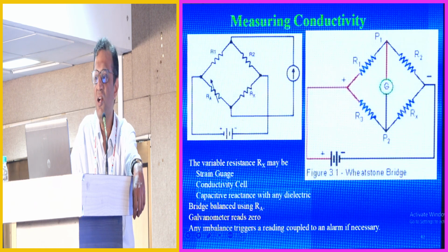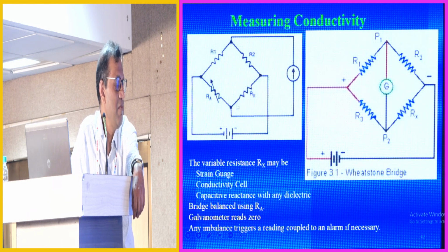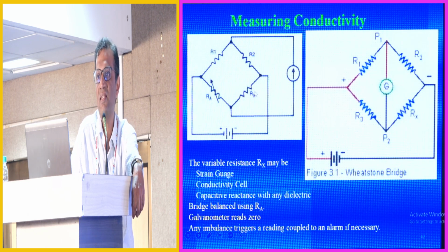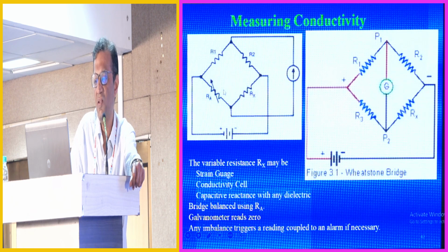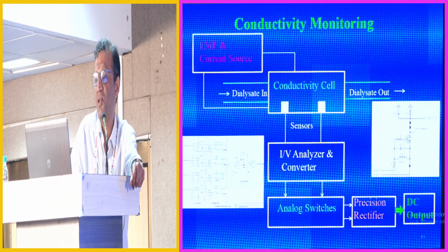So the conductivity cell of a machine is a Wheatstone's bridge. There are two fixed resistances. The variable resistance marked Rx is our conductivity cell with the dialysate, and the adjustment of the conductivity, balancing the bridge to 0, is done with the help of a potentiometer. So this is what happens.